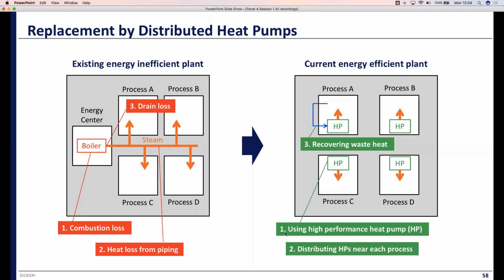The left figure shows the existing plant image. The boiler is located far from the heating processes as a centralized system. This offers easy handling, but energy inefficiency. Long steam piping causes heat dissipation. The right figure shows the replacement by distributed heat pumps.